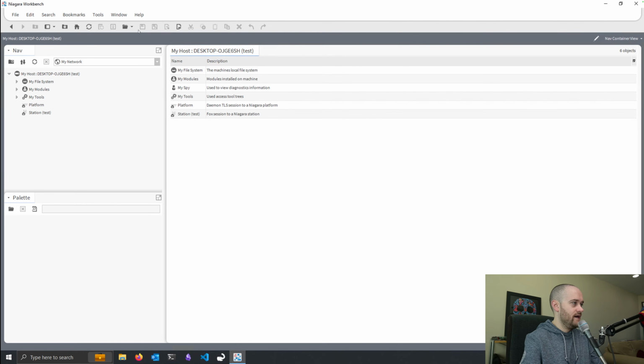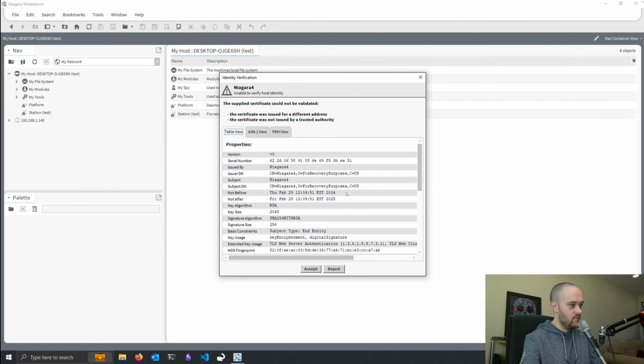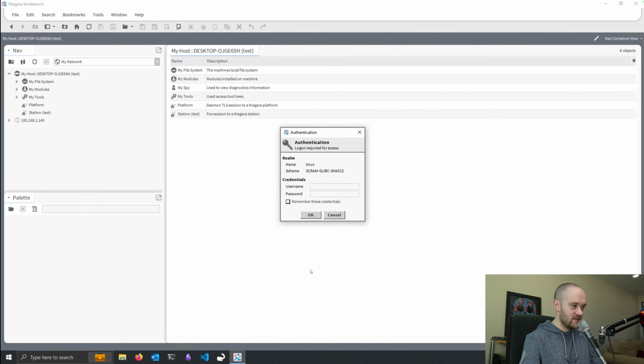Okay, so we go back to Niagara now, and we open up our platform, TLS connection, 192.168.1.140. Okay. It'll come up with the identity verification pop-up. Since this is a new out-of-the-box JACE, there's not really much here to go against to verify that we're getting the right certificate. So we can just hit accept here on this. And then it's going to ask us for the username and password for the platform. Since this is a Vicon JACE, it's just going to be Tridium Niagara.